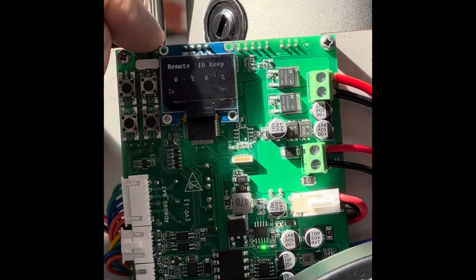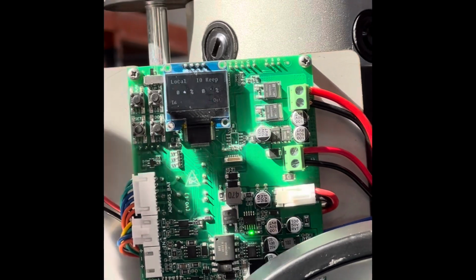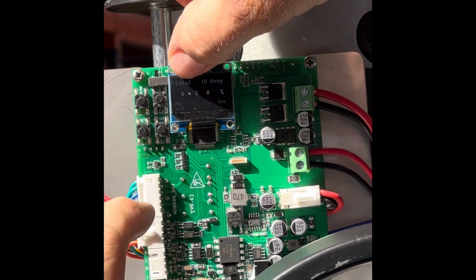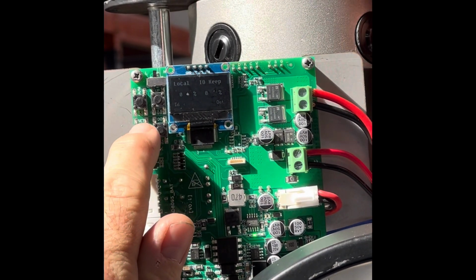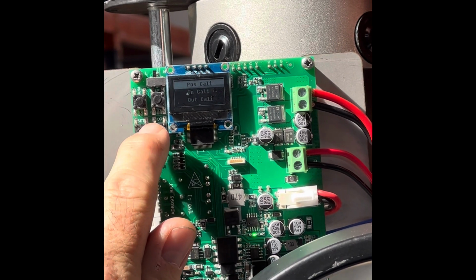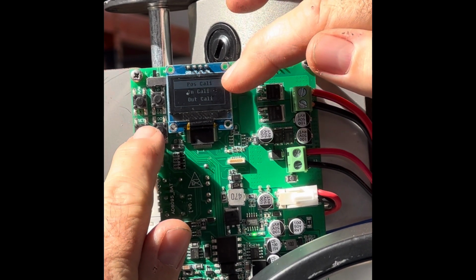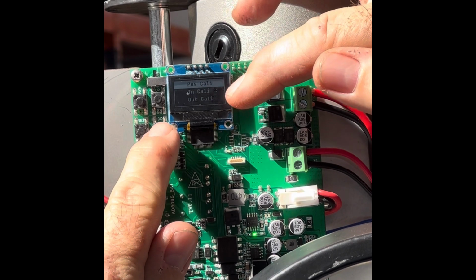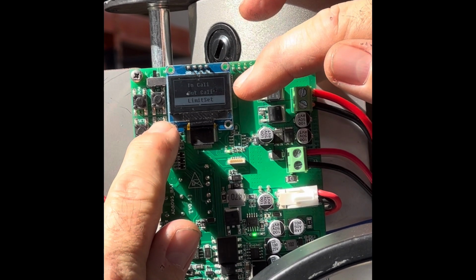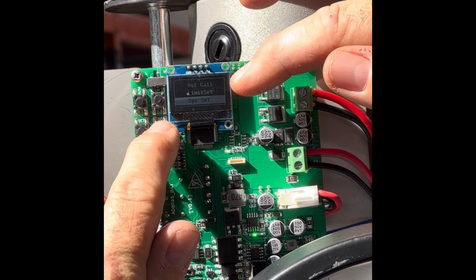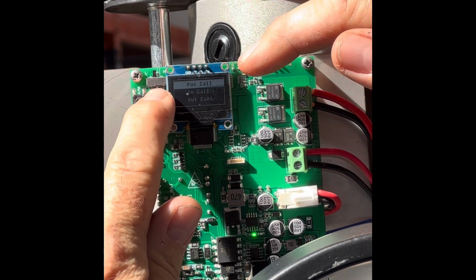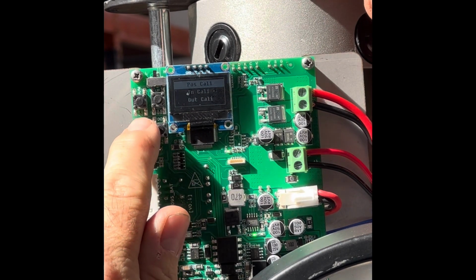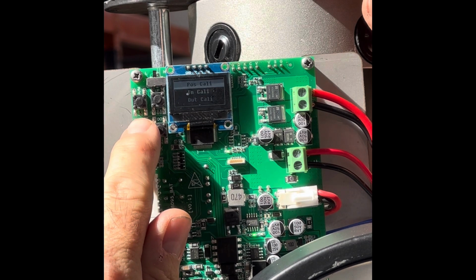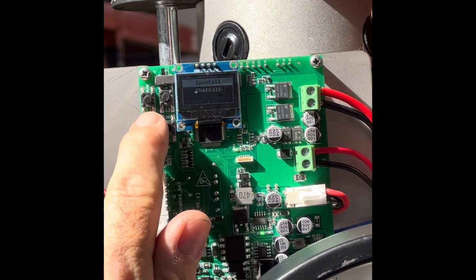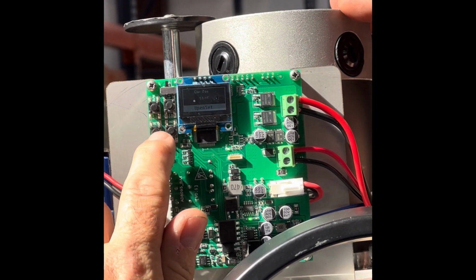So we'll just walk through the calibration stage first. So I'm going to put it in L. Now it says local, keep, hit the set button to enter the menu. Now I see Pos Cali, in Cali, out Cali, limit set, and system set. We're going to do Pos Cali to calibrate the positions, the open and close. So I'll hit set and do the open position, set.